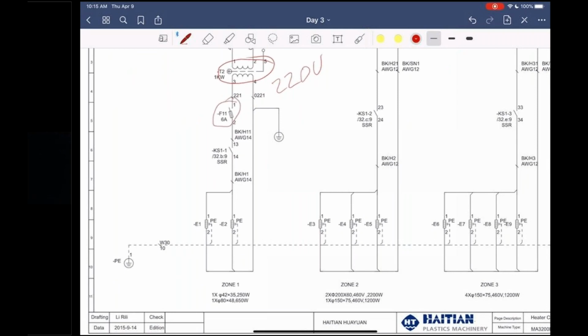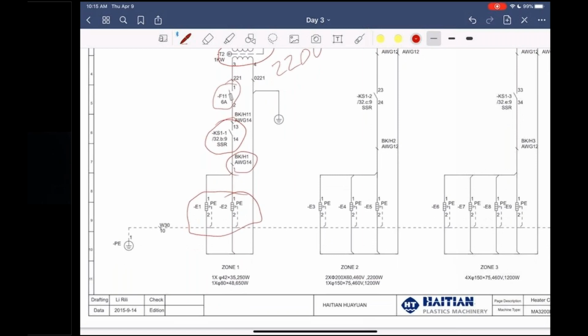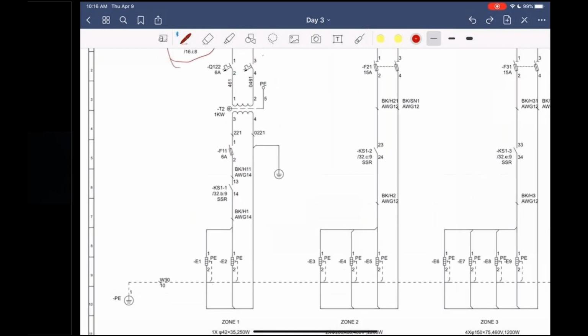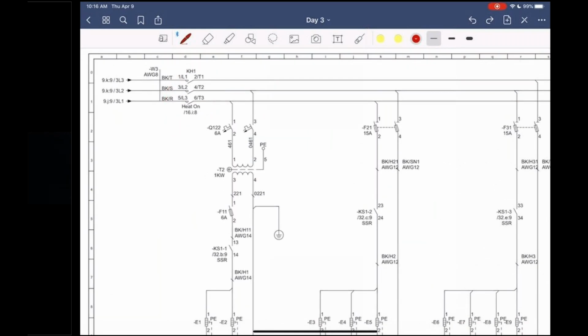And that's protected by F11, a 6 amp fuse, your SSR, KS1, that's using American wire gauge 14, and you have your 2 nozzle heater bands. Keep in mind that the heater bands are grounded. That presents a problem. Number one is for safety, but if the heater bands ever short out, what happens sometimes is because the power is going to complete a circuit, the heater bands will keep heating up even though the SSRs are not calling for the power. So when you're troubleshooting the heater bands, make sure you know that the heater bands are not shorted out to the side of the heater band itself.